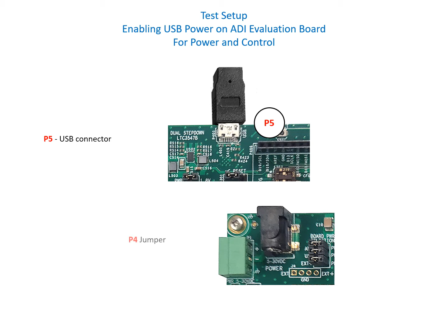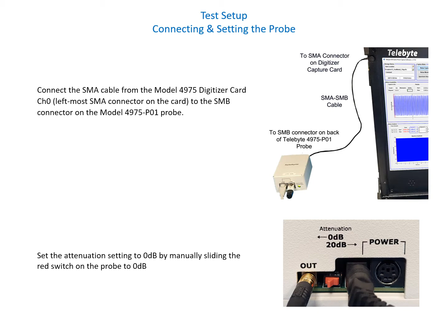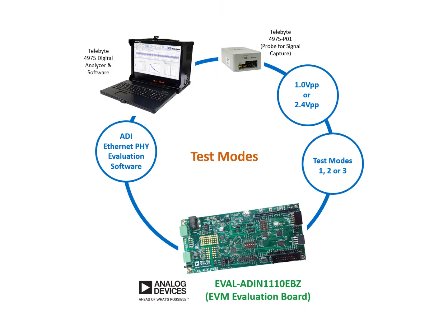Next, we need to connect the probe to the 4975 digitizer card. This is done by using an SMA to SMB cable, which is connected to the digitizer card and also to the back of the 4975 P01 probe. Then we need to set the attenuation to 0 dB. This is accomplished by manually sliding the red switch on the probe to 0 dB. Let's take a look at the software in action.